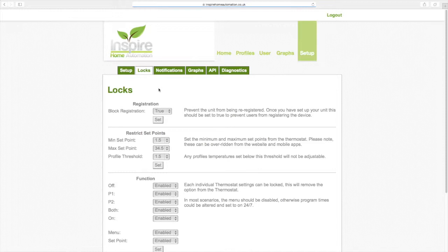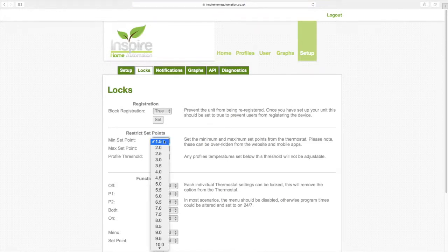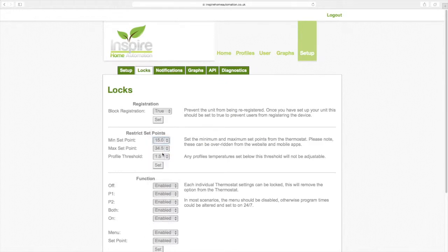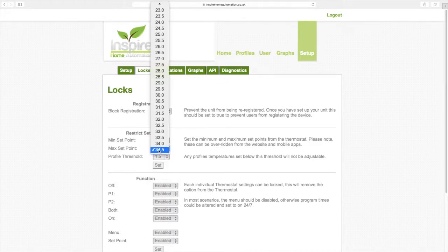Restrict set points allows you to set a minimum and maximum set point. This is great to prevent the heating from being pushed up to 35 degrees all the time. In this example, we are going to set a minimum of 15 and a maximum of 22.5 degrees.